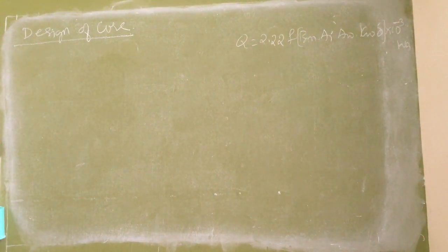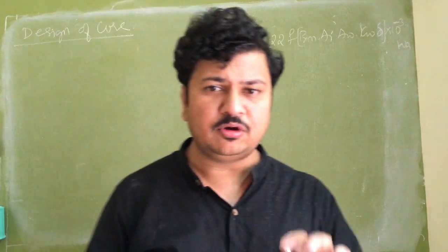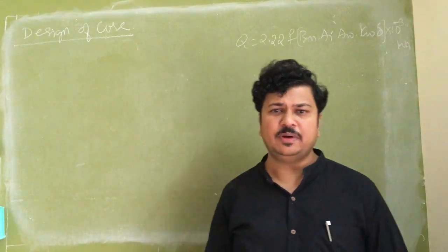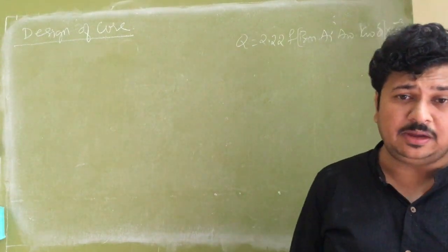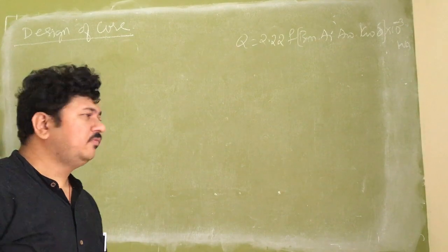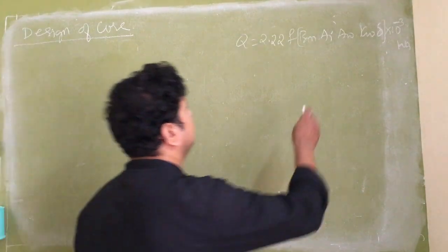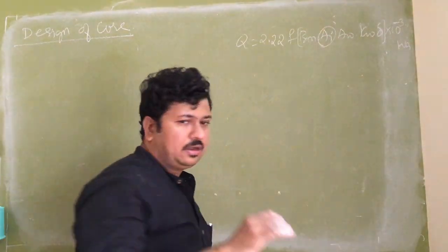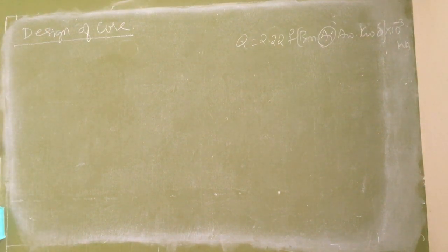This was easy in rotating machines because by default they are cylindrical, so I had to find only the diameter and the length. But here that is not the question. The core area Ai completely depends upon what shape of core cross section I will be using.